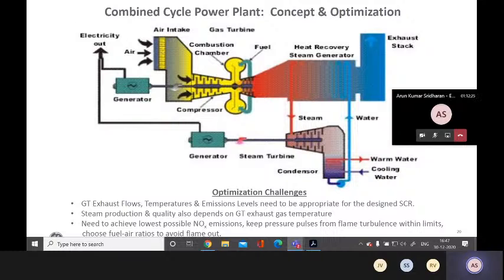You also need to achieve the lowest possible NOx emissions for regulatory purposes. Even though this power plant is now secondary to renewables, it still needs to produce the least amount of NOx to stay below regulatory limits, while keeping the turbine from reaching acoustic limits and flame-out limits. Those are the challenges you face designing and operating a combined cycle power plant much more flexibly.